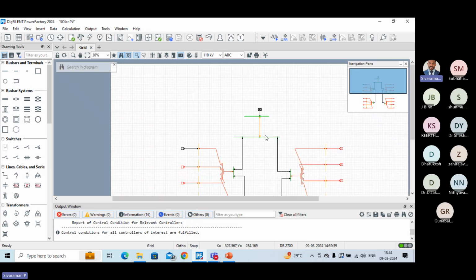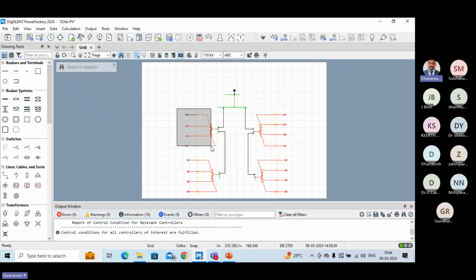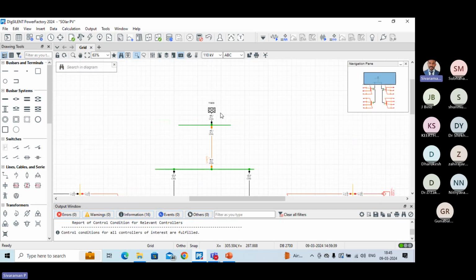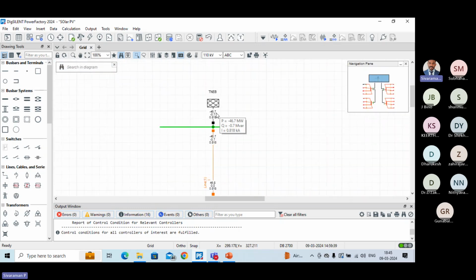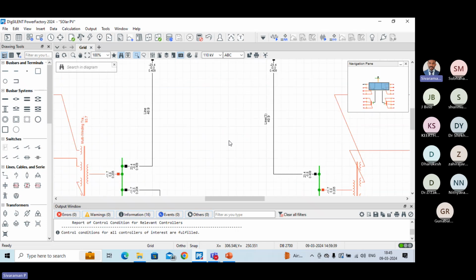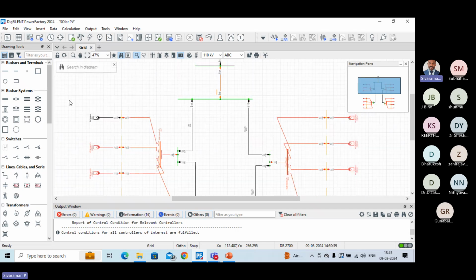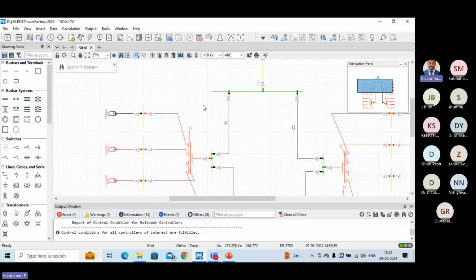If we add one more block like this, or we have to add a minimum of another 4 megawatt into it, then it will become 50 megawatt. So we have to maintain the minimum requirement of 50 megawatt. For that we have to add one more inverter block. We have to add one more inverter in this plant, so that we are able to get this.